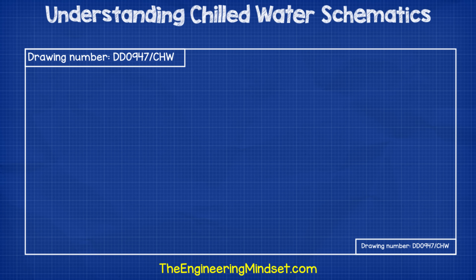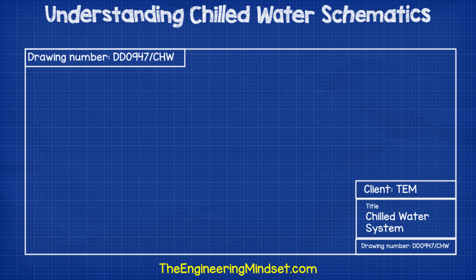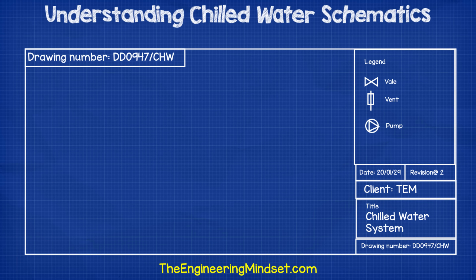How to read the drawing: in the top left and the lower right, you'll usually find the drawing number, which is a unique ID for that particular drawing. In the bottom right, you'll also find the title of the drawing, for example, chilled water system. You'll also find the date of production, the revision number, and other information such as the client and the organization that produced the drawing. And most importantly, on the right-hand side, you should find the legend, which lists all the symbols used as well as their title.